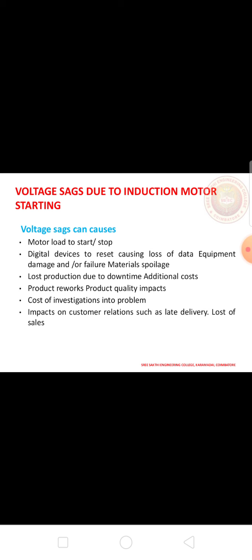Next, the voltage sag due to motor starting. When a voltage sag occurs, the local utility is usually blamed, but many voltage sag events are caused by equipment within the plant. So power quality problems occur on both sides of the electrical meter. The voltage sag produced by induction motor starting current is one of the main causes of sensitive equipment dropout. Next, the subsequent connections at full load produce a new sag, calculated a few seconds later. Next, the use of a motor starter reduces the voltage sag depth but increases its duration.